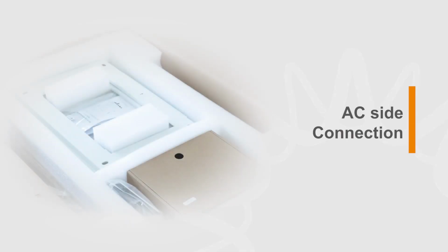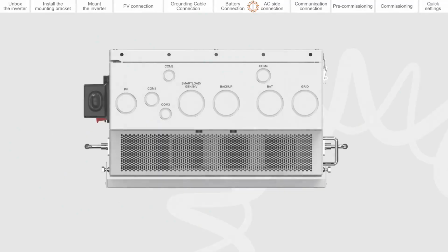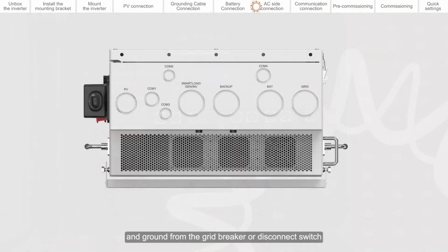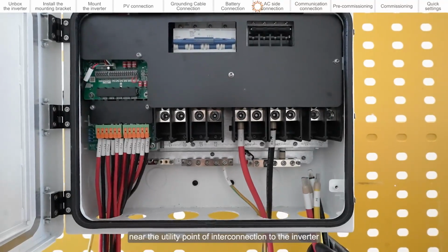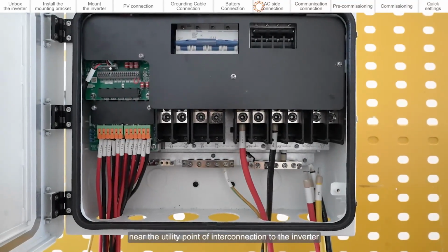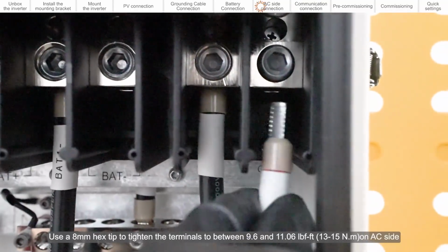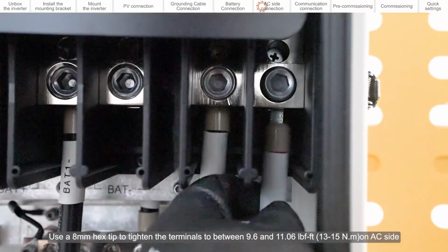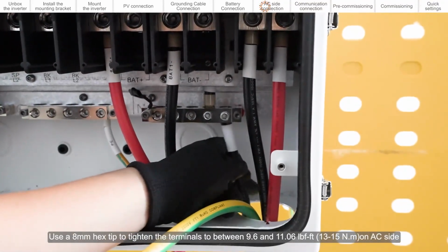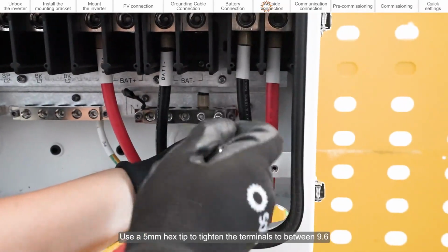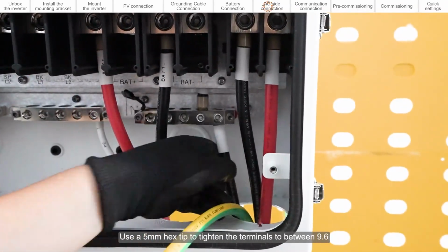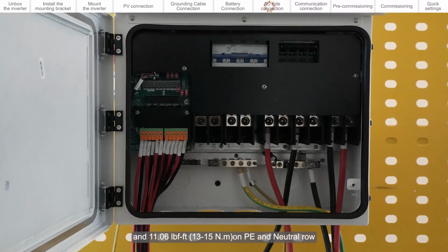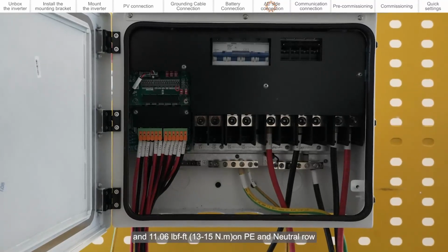AC side connection. Run 4 conductors for L1, L2, neutral, and ground from the grid breaker or disconnect switch near the utility point of interconnection to the inverter. Use an 8mm hex tip to tighten the terminals to between 9.6 and 11.06 lb-ft on the AC side. Use a 5mm hex tip to tighten the terminals to between 9.6 and 11.06 lb-ft on the PE and neutral row.